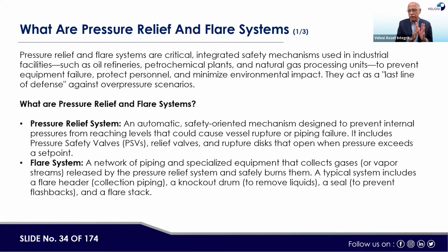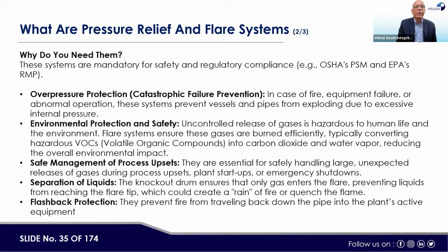The relief system sometimes could be open to atmosphere if it is a non-toxic gas like steam or water. But if it is a hydrocarbon or anything toxic, then it has to be linked to the flare system so it can be burnt. And the flare system is a knockout drum and a chimney, or the burn pit, where these chemicals or hydrocarbons can be burnt safely.